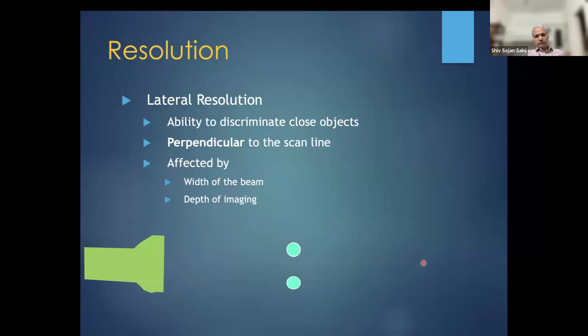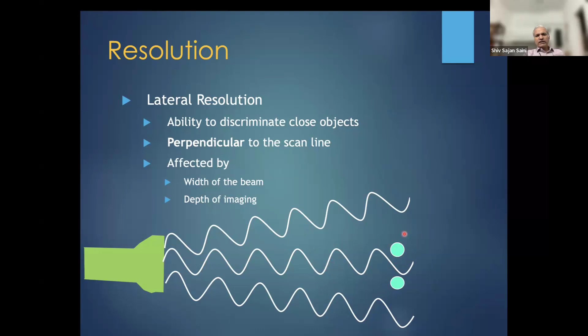On which factor will it depend? Suppose this is the single wave which is going. Now, if they are interrogated by different waves, it will consider these two structures as two different structures. But what happens in real time? In the neonates, we use the phased array probe, which has a very small footprint. And the waves, when they go inside, they diverge. Because of this divergence, as you have seen in the previous slide, it forms a sector kind of visual display on the screen, on the user interface. So once they go apart, lateral resolution is likely to be compromised.